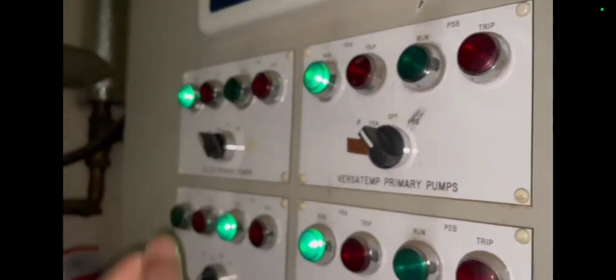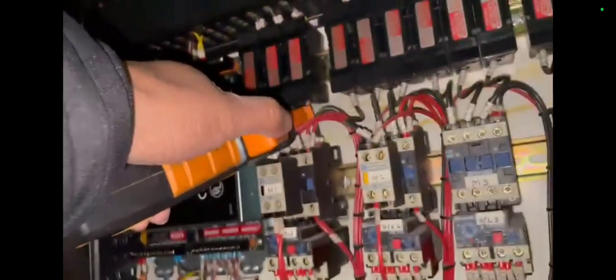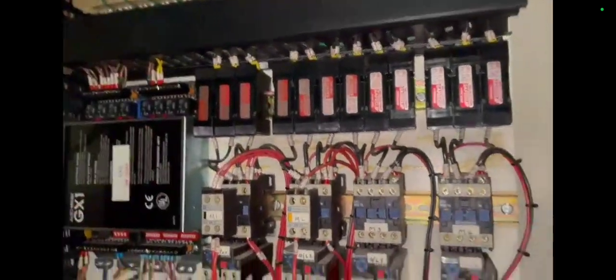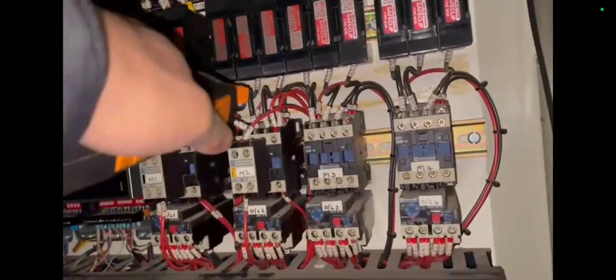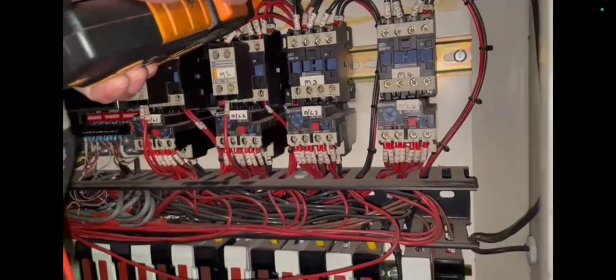And then pump one, phase three. And what do we have here? We have 1.34. So 1.4, 1.34, phase one was different on pump one. So I'm believing that pump one has got a problem. It should be sent back.